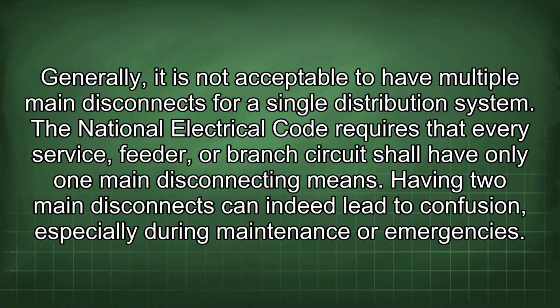Generally, it is not acceptable to have multiple main disconnects for a single distribution system. The National Electrical Code requires that every service, feeder, or branch circuit shall have only one main disconnecting means. Having two main disconnects can indeed lead to confusion, especially during maintenance or emergencies.